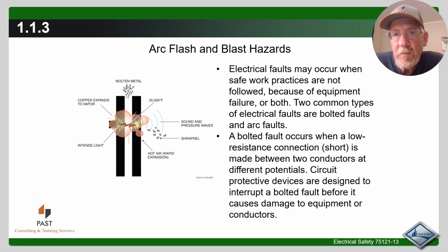Electrical faults may occur when safe work practices are not followed, because of equipment failure, or both. Two common types of electrical faults are bolted faults and arc faults. A bolted fault occurs when a low resistance connection or short is made between two conductors at different potentials. Circuit protective devices are designed to interrupt a bolted fault before it causes damage to equipment or to conductors.